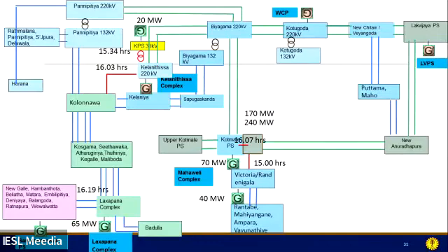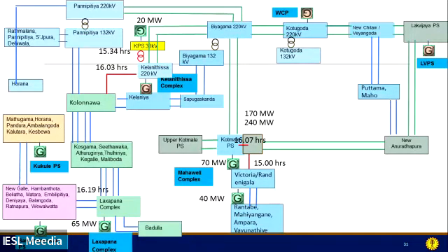During the last restoration process, we were unable to restore the southern system successfully because of frequent tripping of the southern-side generation, so it was not restored as an island system. We restored that part by connecting the southern system with the Laxapana system. Then finally, from the Kukule power generation, the Matugama and Ambalangoda substations were restored in parallel. It was synchronized with the rest of the system at 1635 hours from the Matugama to Horana transmission line. That's how we restored the system in parallel.